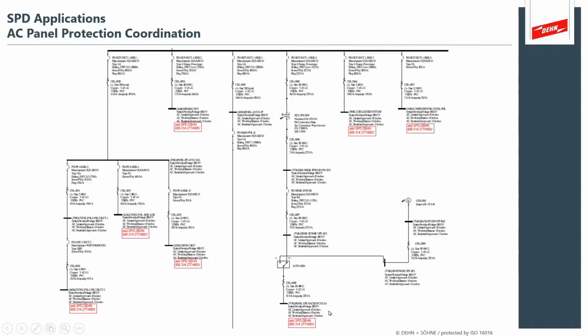So you'll have absolutely mandatory things like sump pumps on job sites that have their own backup generator, so that during the lightning storm, the surge of the rain is also causing you issues in your drainage systems. You don't want to lose your sump pumps in these emergency situations due to flooding and lightning. So you'll often see these transfer switch applications, and we recommend coordinating and putting surge protection on the downstream side of what is clearly an emergency service application.